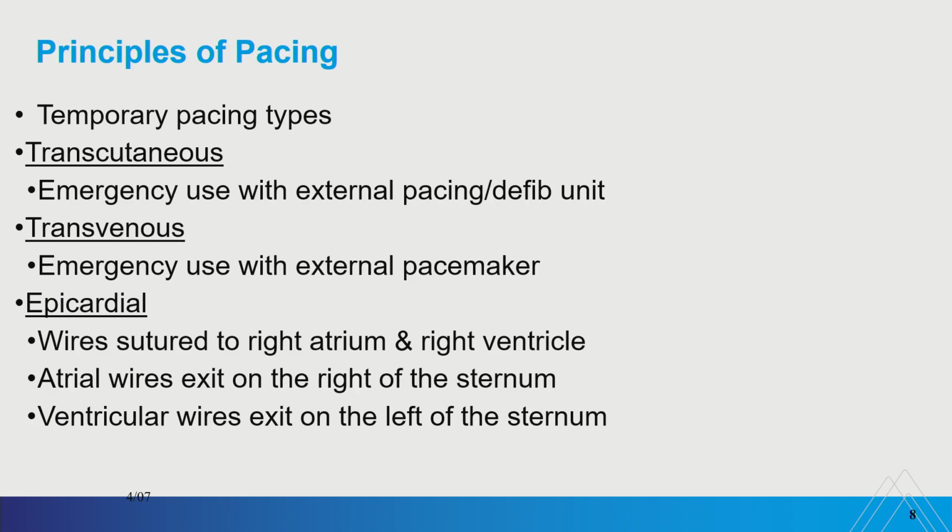We've run into a situation where I've walked into a unit and I just saw ventricular spikes across the screen with an idioventricular rhythm underneath. And when I asked the nurse, what's going on with that pacemaker? Oh, well, the patient was complaining so much that it hurt, so I turned down the mA and I figured it was better than nothing. It wasn't, it was worse than nothing.